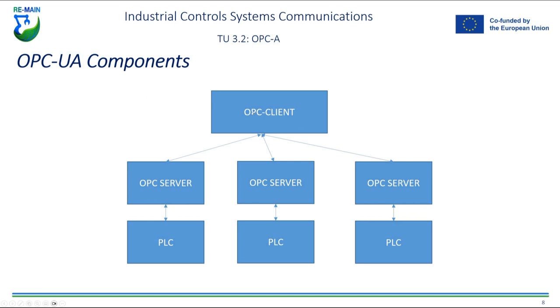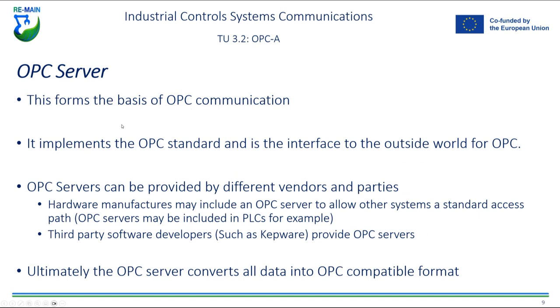The OPC UA components include the OPC client, OPC servers, and the assets that interface with the server. The client can get data via the OPC server, and that data can be related to any factory-based asset communicating with an OPC server. The server itself forms the basis of OPC communications, implementing the OPC standard as the interface to the outside world. Servers can be provided by different vendors — many hardware manufacturers now include an OPC server to allow other systems a standard access path. For example, within your PLC, you can set up the PLC to have an OPC server so clients can interface with it and get the data they require.